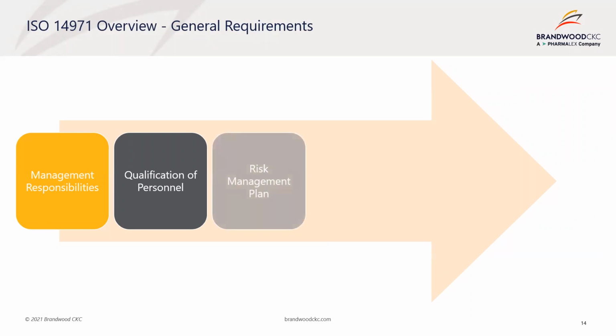The standard requires that manufacturers establish a risk management plan. This is a living document that must be maintained for the life of the product. It describes the scope of the risk management activities, the responsibilities and authorities of those involved, the criteria for risk acceptability, the production and post-production information to be collected and reviewed for the medical device, and all the risk management activities that are carried out during the entire product life.